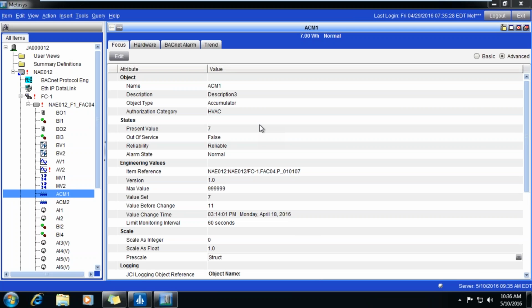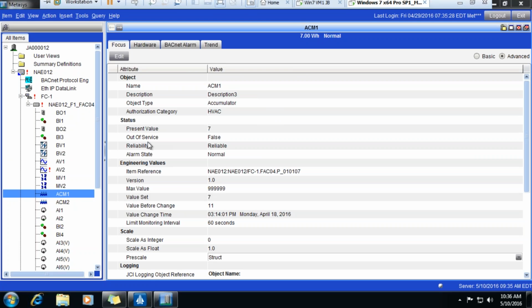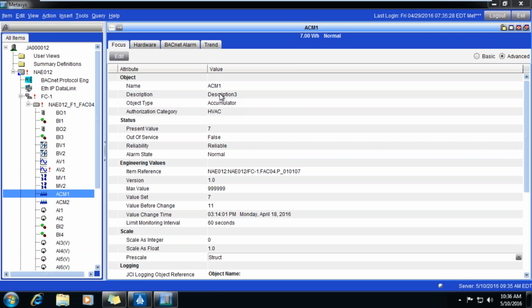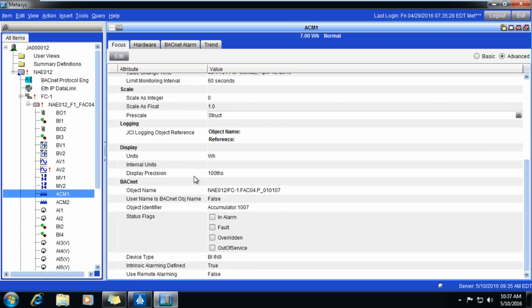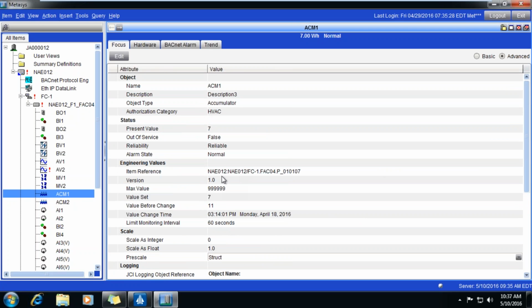So here I have what's called an NAE, and this is from Johnson Controls. NAE stands for Network Automation Engine, and it's a device that supports BACnet, and it does building control. This is actually a device that we have on site here at our Kepware headquarters. And here I'm looking at a couple objects in the NAE. I'm looking at an accumulator object. That's one of the objects that Glenn just described, and it can give you all different types of information about consumption and information over a period of time. So you see here the different attributes of the object represented. For example, present value 7, value set 7, and so on and so forth.